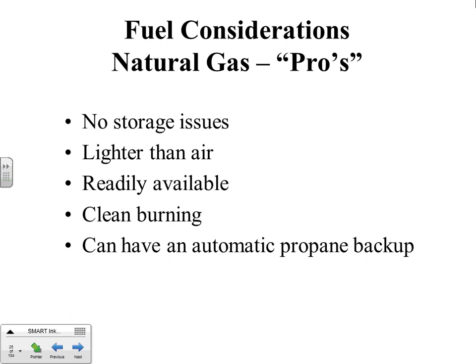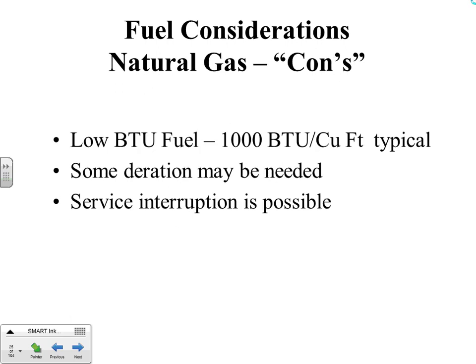And that's done because of a National Electrical Code requirement. You have to have a 2-hour on-premise supply. And in California and other seismic areas, it becomes very apparent that you could actually, in an earthquake, rupture that natural gas line. So the option to make this system a legal system is to have a propane backup that'll automatically switch over in the event of a rupture. And it does that through pressure sensors in the lines and stuff. On the negative side for natural gas, it's a low BTU fuel, contrasted to some of the others. 1,000 BTU per cubic foot is typical from the suppliers. Some deration may be needed, contrasted to propane. Service interruption is possible.